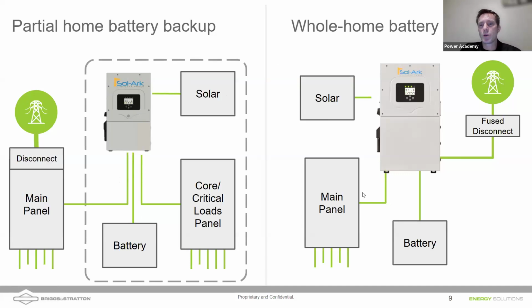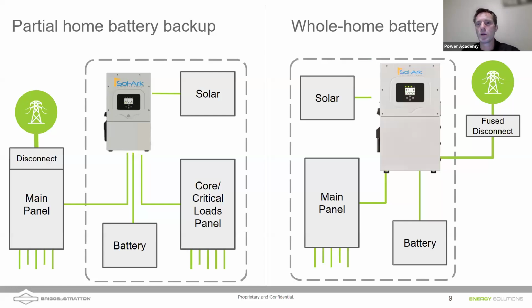But for whole home backup, we're looking at backing up the full main panel. And one of the nice things about the Sol-Ark 15K is it has 200 amps of built-in pass-through. So you put your disconnect between the utility service and your inverter. You're able to pass 200 amps right through, if the grid is active, to your main panel. Grid outage. Well, then the inverter isolates itself from the grid, so we're not sending power back onto lines that linemen might be working on. And the battery is now discharging, powering the home.